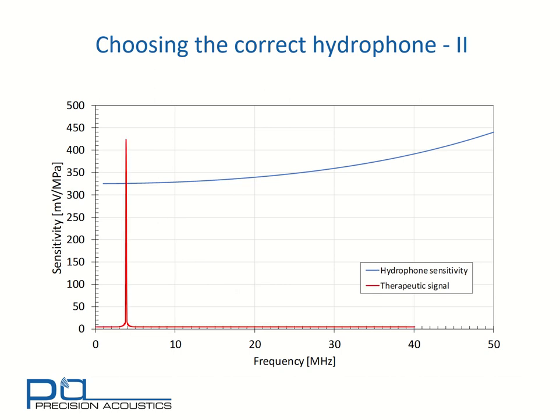We'll now consider the therapeutic signal with the membrane hydrophone. This has got a very narrow spectral range, so again one would consider that the hydrophone may be appropriate for this measurement. However, the long signals associated with therapy signals can sometimes drive membrane hydrophones into resonance. So whilst frequency response is important, it's not the only consideration.